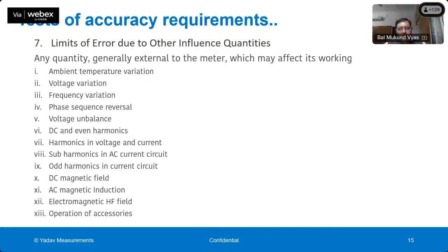So the meter under reference condition is tested with a current of exactly 50 hertz and a sinusoidal voltage without any harmonics. But here we are testing how the meter's accuracy is affected if there is a DC content in the current, or the current has even harmonics. So this is even harmonics. In this case, there are harmonics only in the current circuit. There are no harmonics in the voltage circuit. In the next case, we are testing the meter's accuracy when harmonics are present in both voltage and current circuits. So how the meter measures the energy when there are harmonics or subharmonics or odd harmonics present in the load and voltage circuit.